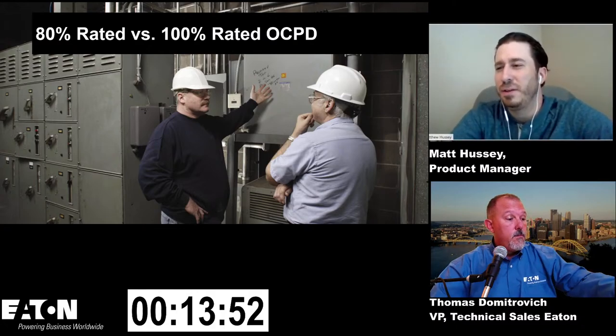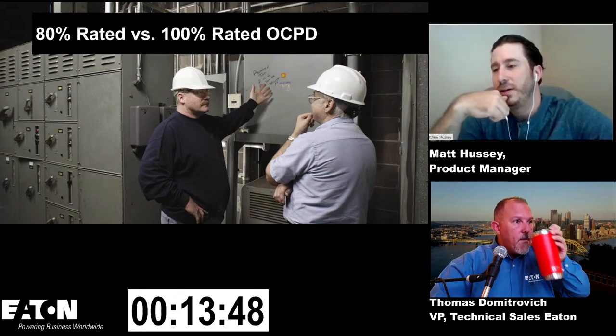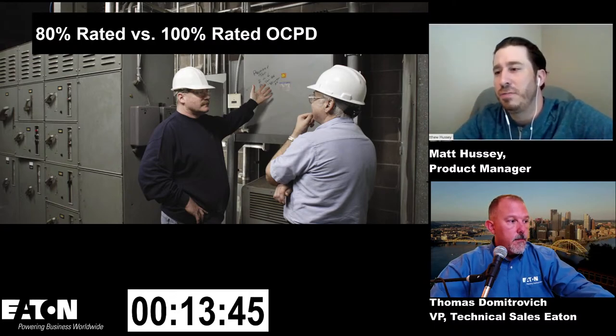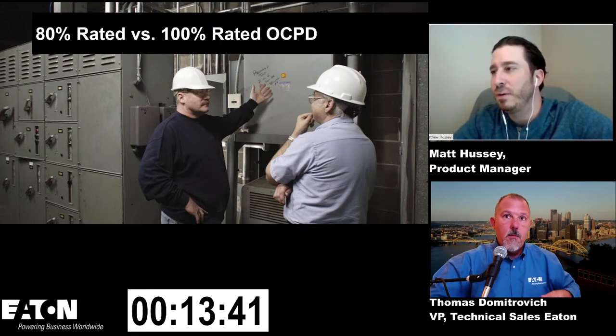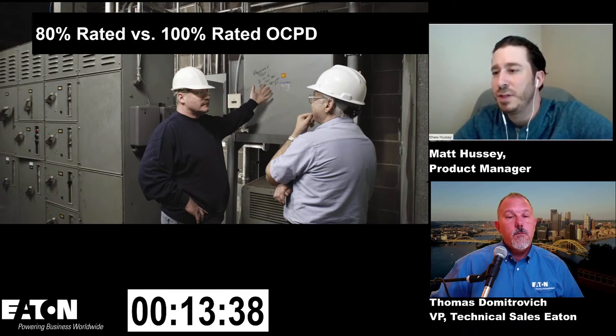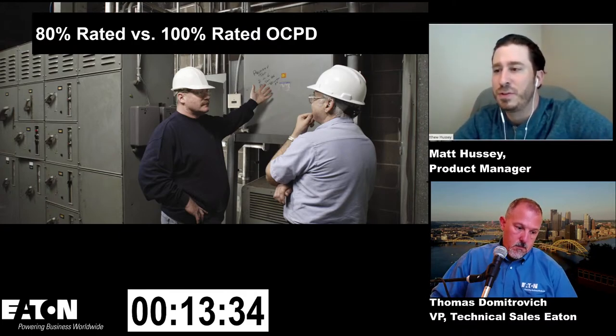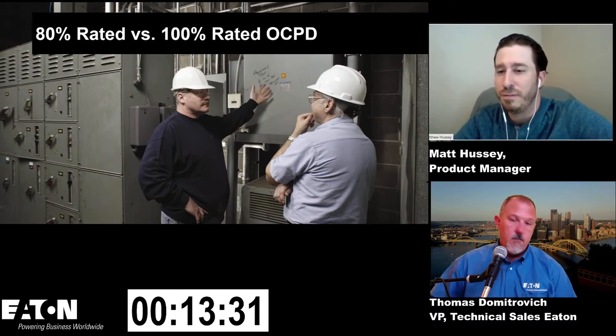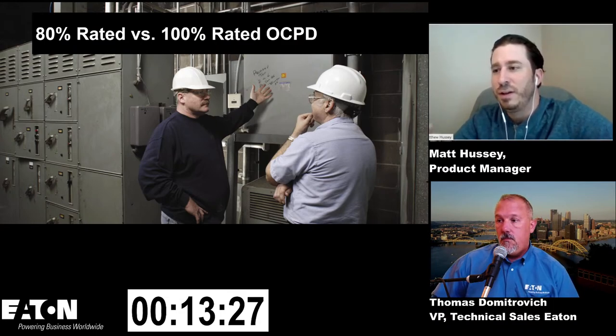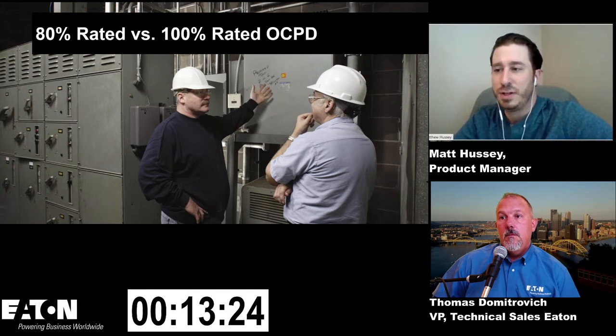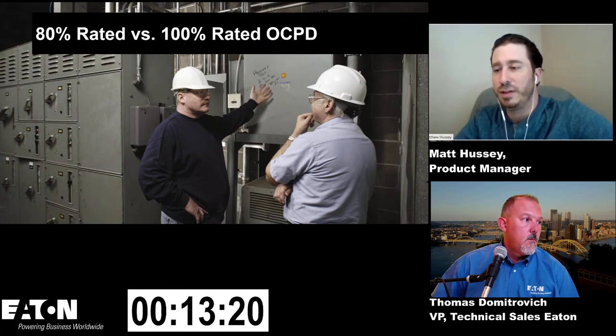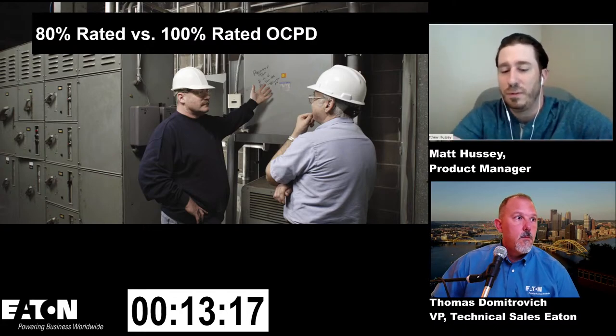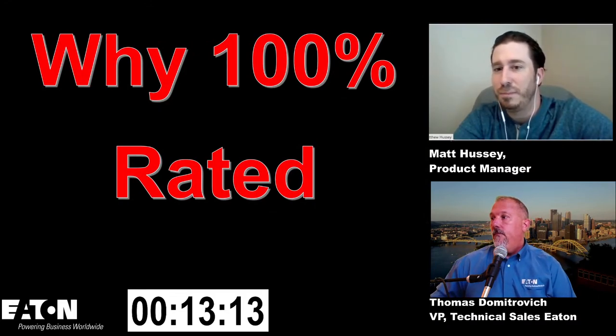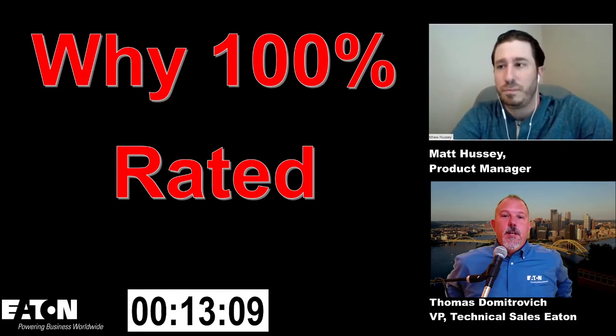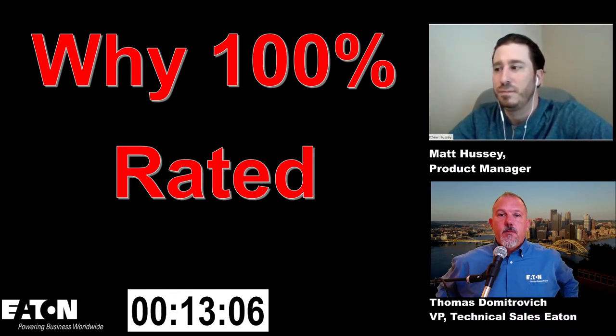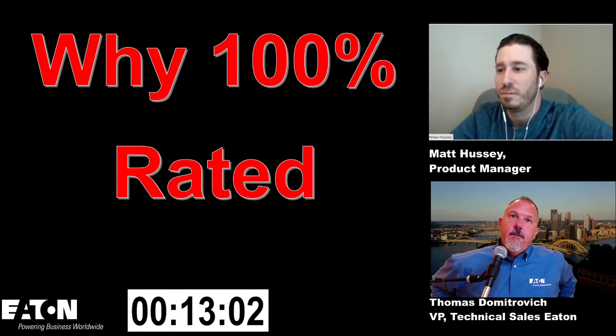Yeah, I see it a little bit from the other end too, where there'll be an effort in the design phase of wanting to incorporate a 100% rated disconnect inside the equipment. And so there's some confusion around how you size the overcurrent protective device for the application. And so obviously there are significant implications there, where the equipment has to be designed accordingly. So hopefully we can provide a little more clarity around what is meant by 100%. So why would we go to 100% rated solutions? What's the driving factor? Do you have any thoughts on that, Matt?